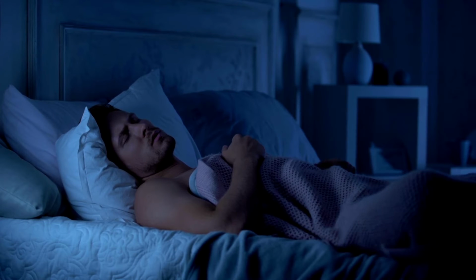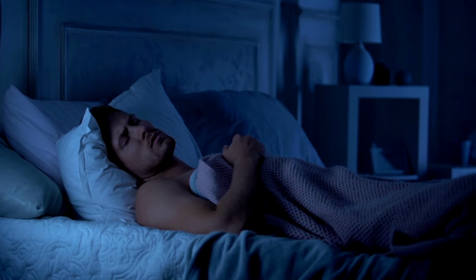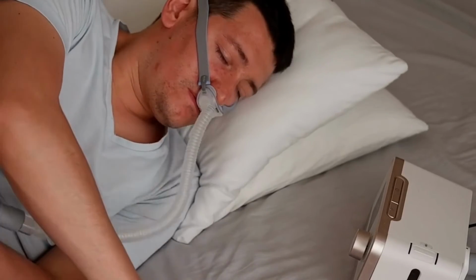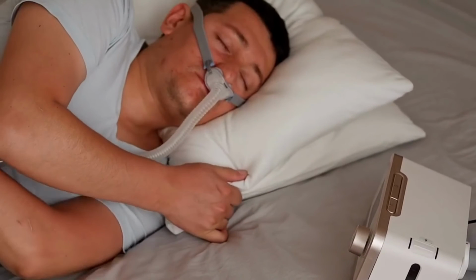Note, some machines also have a smart option which will automatically sense when you fall asleep and start to increase the pressure then. There's a few more comfort settings that some CPAP machines have, so let's talk about those. The first is Smart Start or Smart Stop, and this could be called something else depending on the machine. This feature, when enabled, allows the machine to automatically sense when you're starting or stopping the machine based off your breathing. It monitors your breath, and when you start to breathe on the machine, it will automatically start it, and then once you stop using the machine, it will sense that and automatically turn it off.